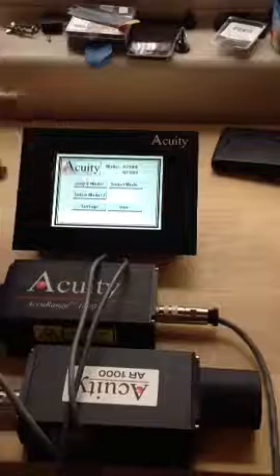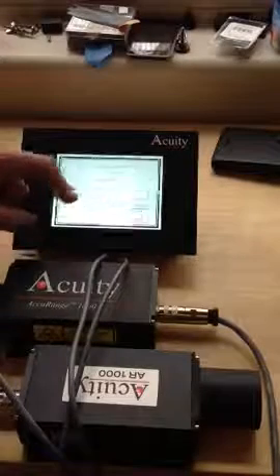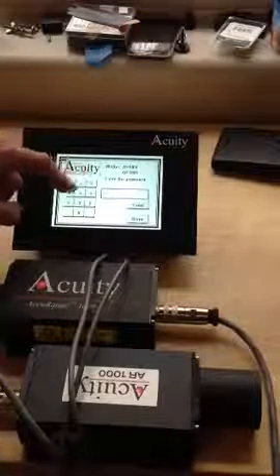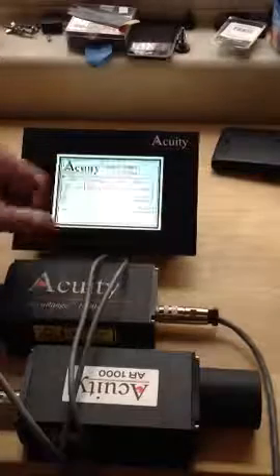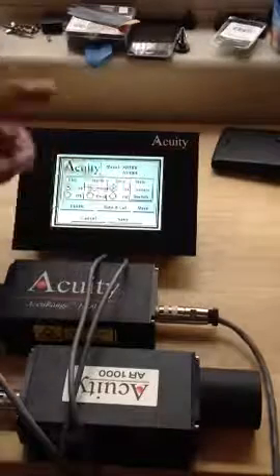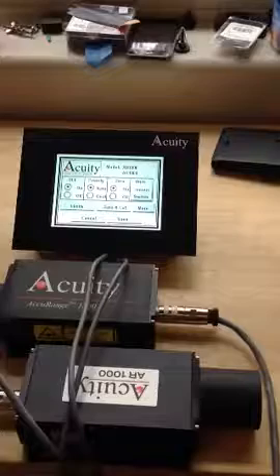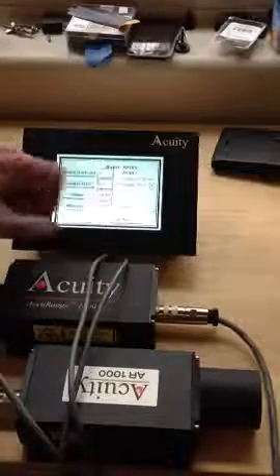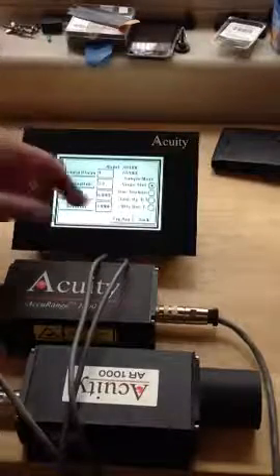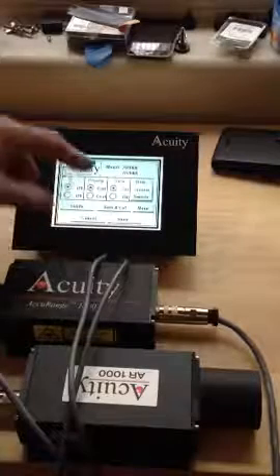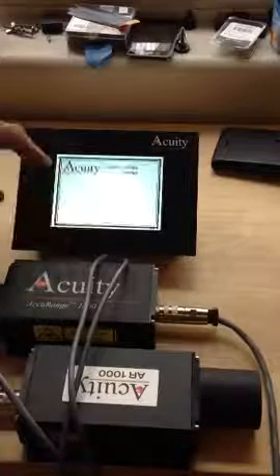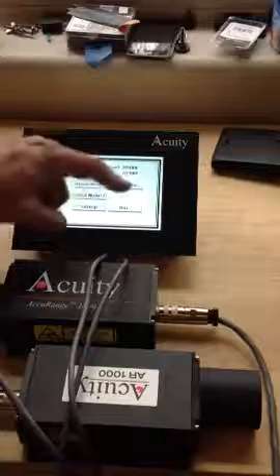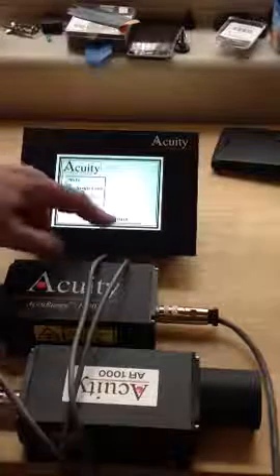I selected the models, AR1000s, went into settings, zero on, have it in meters, both lasers should be in factory default. We put it in the rate and cal standard units, we saved it, and in the select mode, we put in thickness. Simple as that.